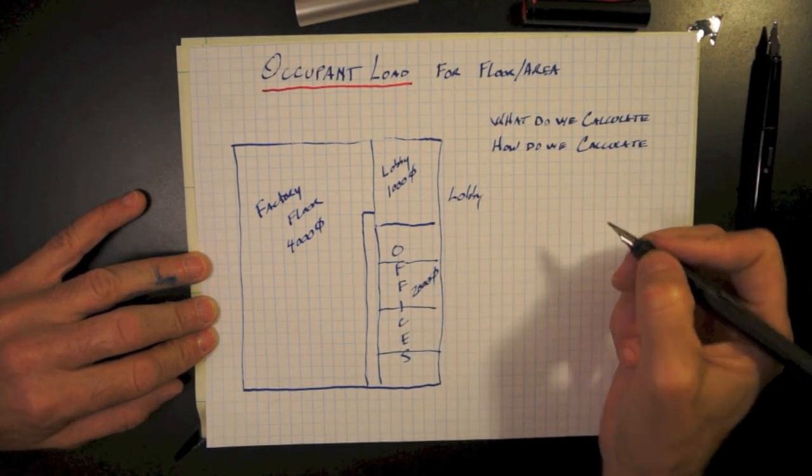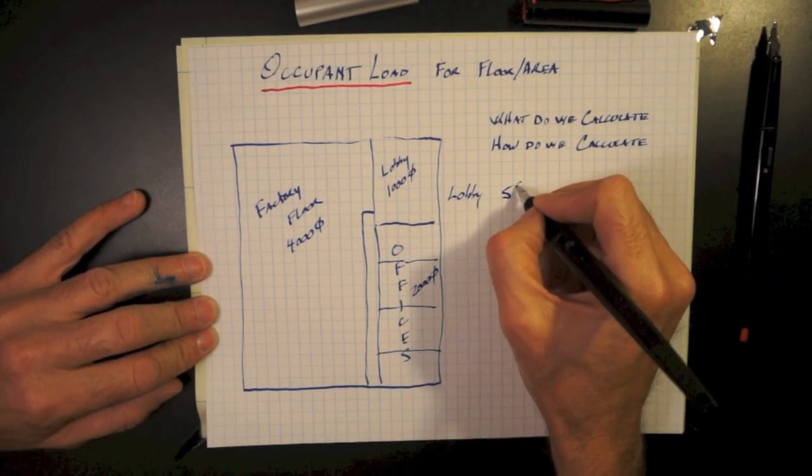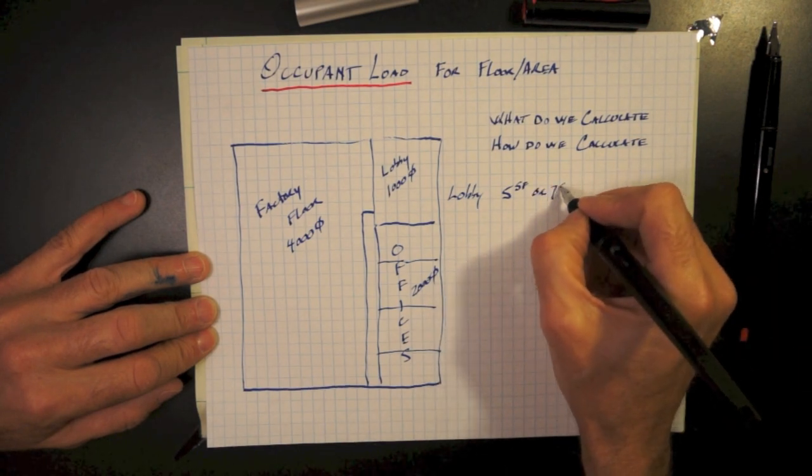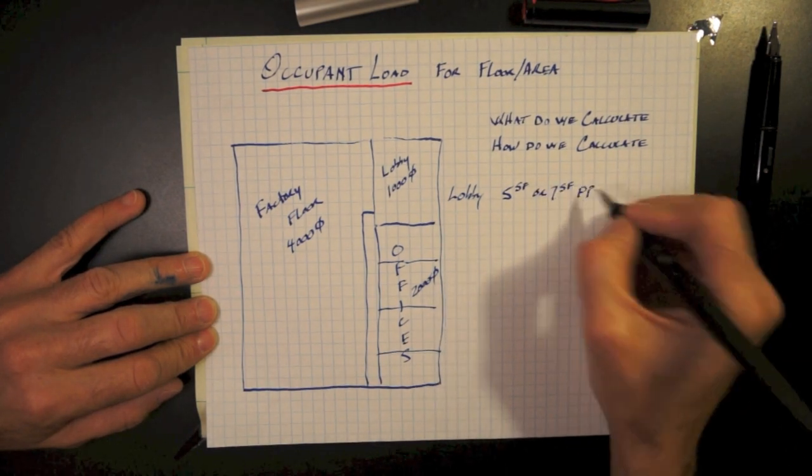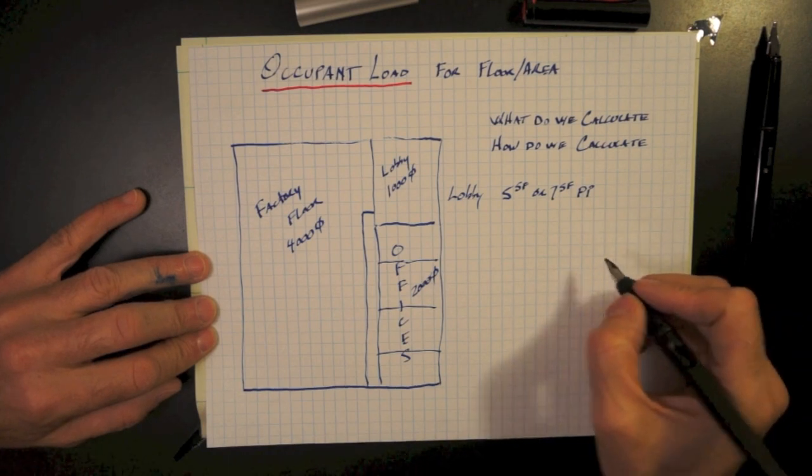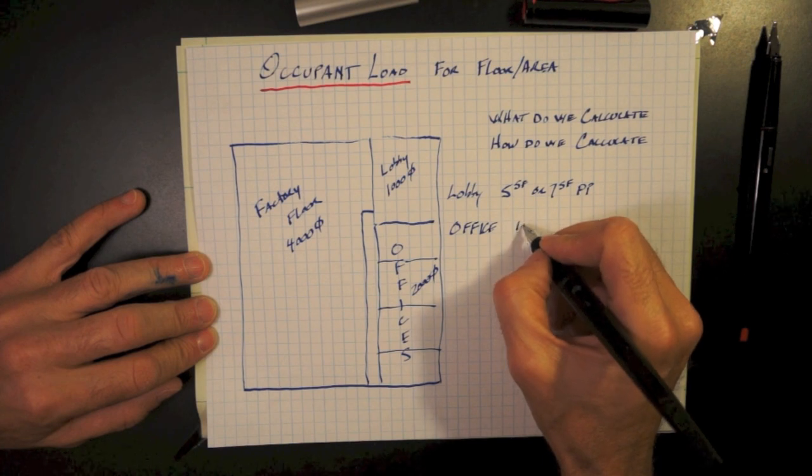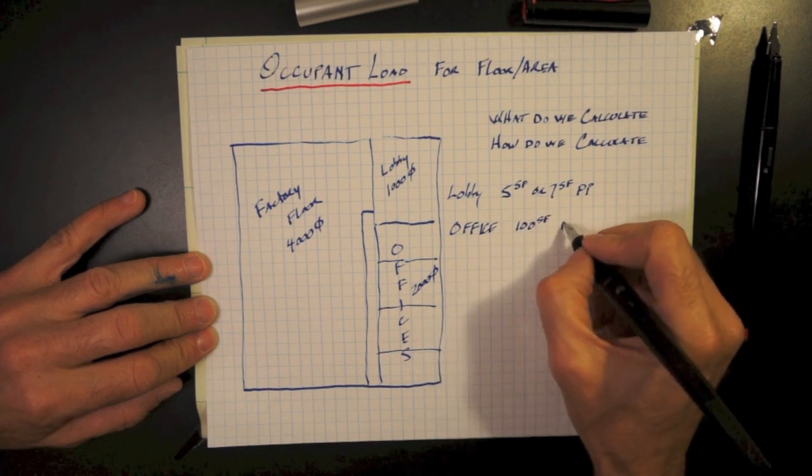The lobby, considered assembly space, could either be 5 square feet per person for standing room only, or 7 square feet per person for tables and chairs. I think the argument could be had for tables and chairs at 15 square feet per person, but we're going to stick with 7 at this time.